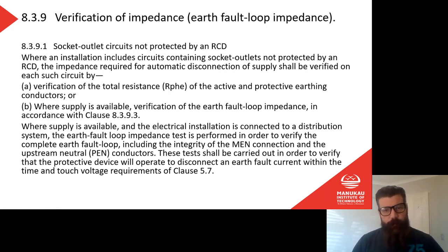Verification of impedance, so the earth fault loop impedance. Socket outlets not protected by an RCD. Where an installation includes circuits containing socket outlets not protected by an RCD, the impedance required for automatic disconnection of supply shall be verified on each such circuit by verification of the total resistance of the active and protective earthing conductors. Where a supply is available, that's where it's switched on, verification of the earth fault loop impedance in accordance with clause 8393. Okay, we need to know a lot more information than we currently do to be able to really figure out what the earth fault loop impedance is.